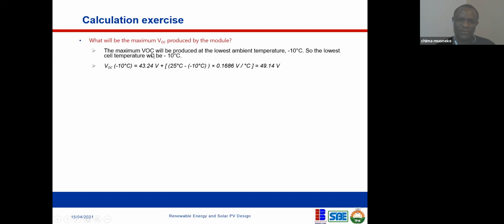So the maximum open circuit voltage will be produced at the lowest ambient temperature. Remember, I said that with every degree rise in temperature, your voltage drops, but every degree drop in temperature, your voltage increases. Okay? So at the lowest ambient temperature, which is -10, that's where you are going to have the highest open circuit voltage. So the lowest cell temperature would be -10.